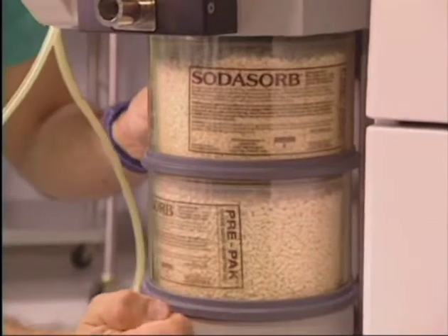At Grand Rounds this year, we had a discussion on pouring water into the absorber, and in our institution, they said not to do that. If you had any concern about it, pretty much take off the lower canister, if not both. Right. And replace it with fresh. Does the insert on the absorber say that you can pour water into it? I don't know. But I know you can. And I know that there's been at least one study that suggests that that works, that you will rehydrate the absorbent simply by pouring water into it.